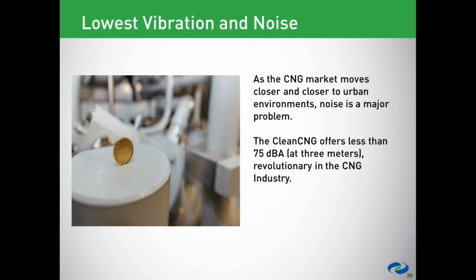One of the key things that we're focused on here is lowest vibration and noise. As CNG markets evolve, and because we're involved globally, we see markets at different phases of their evolution and penetration. But as they evolve, the bigger compressors start to move into the urban areas, and the demand for noise reduction becomes extreme. At the same time, of course, urban environments are becoming much more sensitive to noise levels and regulating them more aggressively. So our focus was on getting the vibration down and reducing the noise levels. And we've achieved 75 dB at 3 meters. We actually see less than that in many cases, but as you know, that depends on many factors. And you can comfortably hold a conversation like we're having outside, standing right beside a unit running full out.